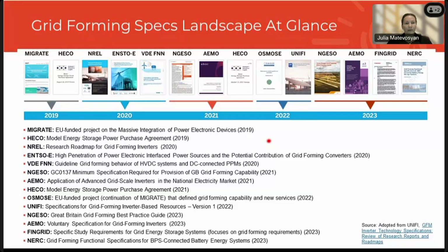And then Hawaii Electric Company, because they are smaller islands, they're facing rapid increase in renewable integration. They already in 2019 came out with high-level requirements for all new battery storage to be grid forming. And at that point, there were just 7 or 8 functionalities that they would require, and there were no more specifics on that. The NREL Research Roadmap also identified functionalities that are important for future inverters, and so did a group that worked at ENTSO-E. And if you look at NREL's and ENTSO-E's functionalities that they defined, they're pretty well aligned.